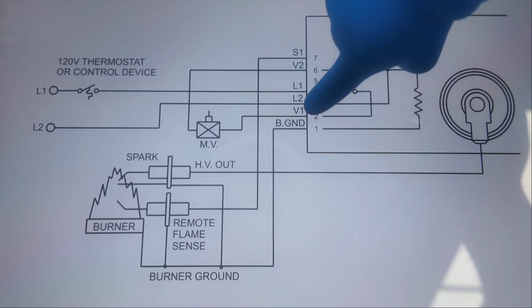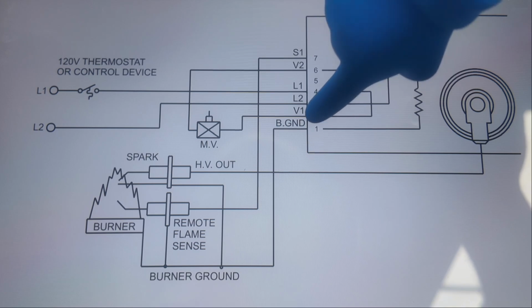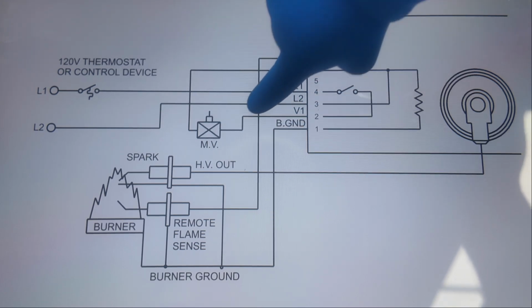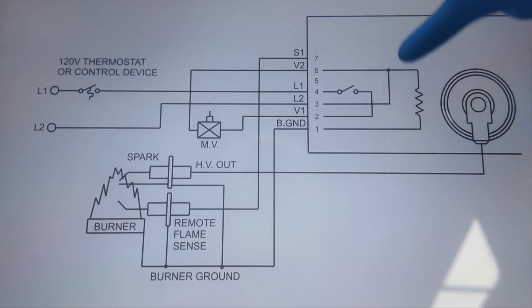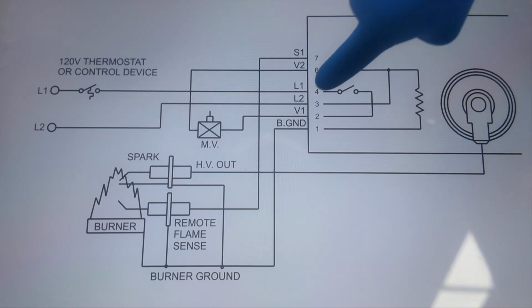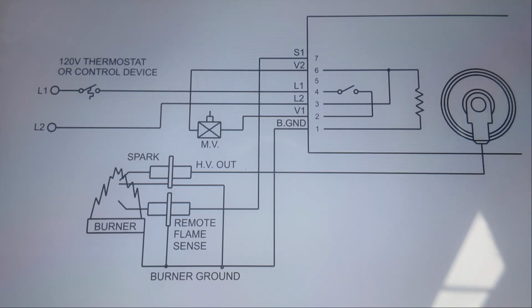Now, one other thing, V1, it shows V1 going straight from the board to the main valve. I would recommend having a 3 amp fuse, a 2 or a 3 amp fuse on the V1 terminal, between V1 and your valve. Because if that valve shorts out, I've seen it, if that valve shorts out, it can fry the board. So if you put a fuse on V1, it will extend the life of your board. It'll last longer.